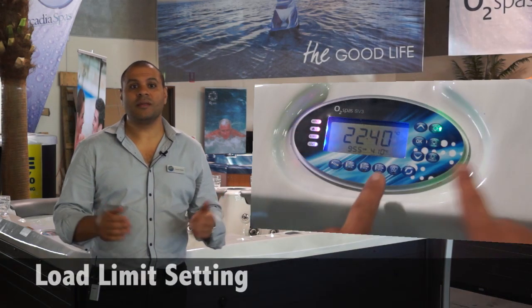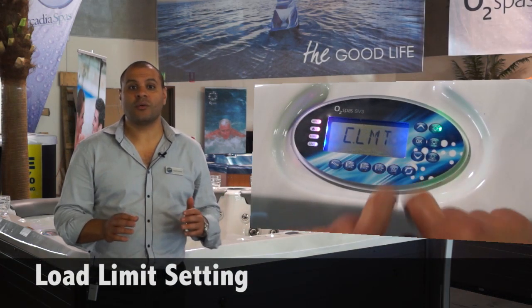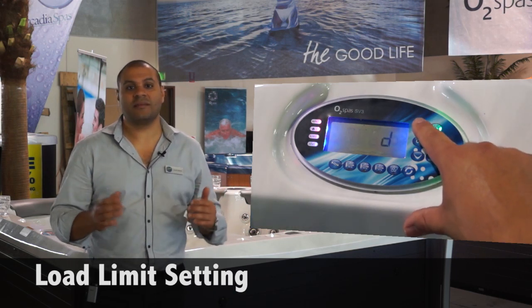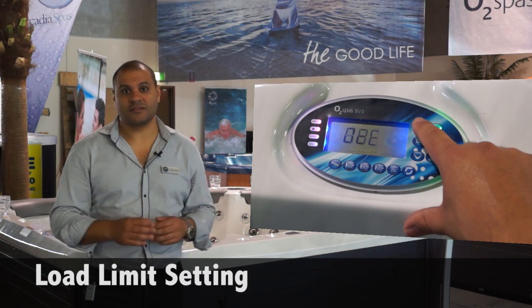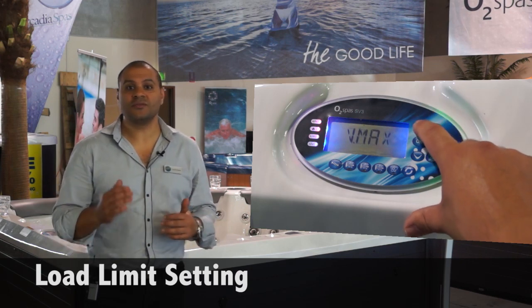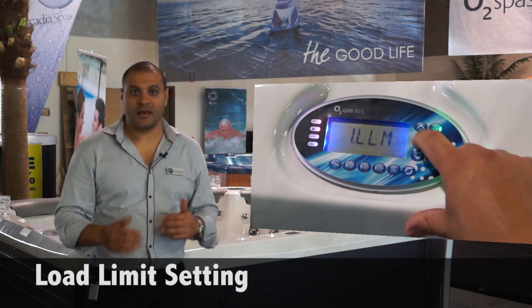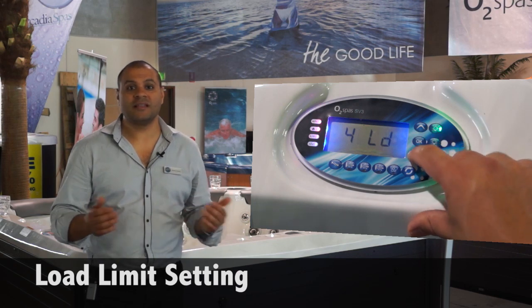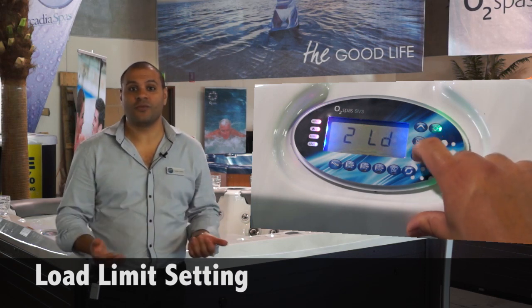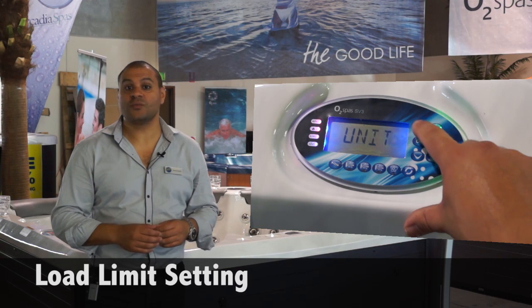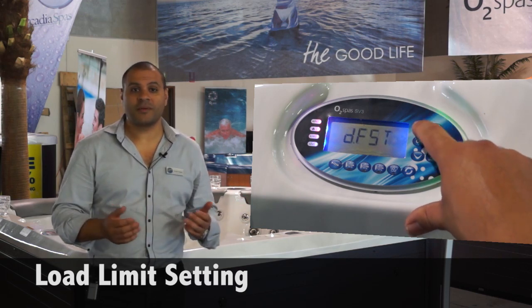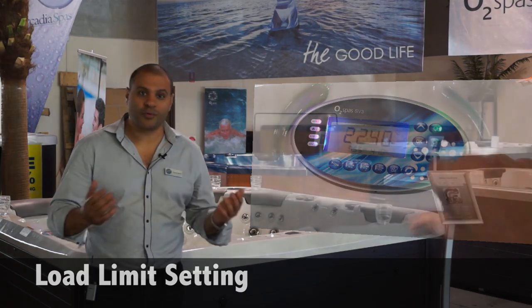To set the load limit setting, press and hold the blower and clean cycle buttons together until you see CLMT, then release the buttons. Next, press the up button until you see ILLM and then press OK. You can see in this video the load limit is set to 4. We will set this to 2 as we only have 20 amps of power, and then press OK. Then scroll up until you see the word exit and press OK.